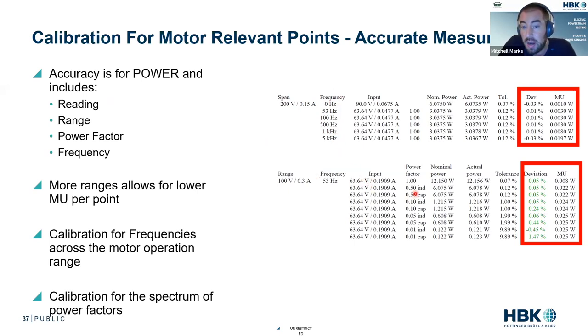We also do that for power factor. We don't only calibrate at a power factor of 1, we calibrate at 0.5, 0.1, 0.05, 0.01. These are really hard measurements to make. We're very proud of how accurately we can make these measurements. And I say that to, again, try to give you the confidence that HBK can be a partner for determining your measurement uncertainty and for giving you the best, most accurate measurement possible.